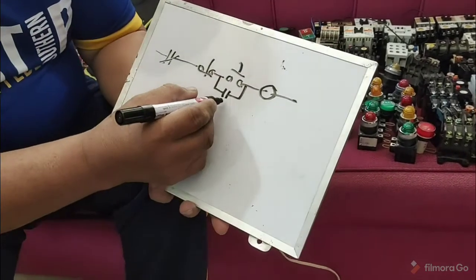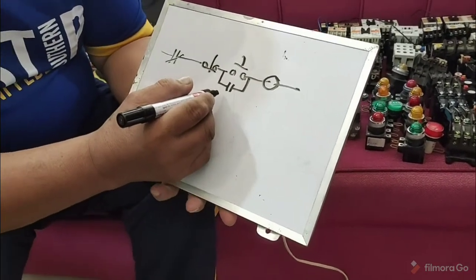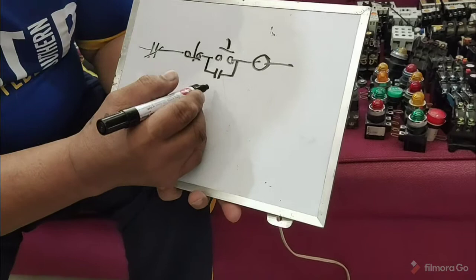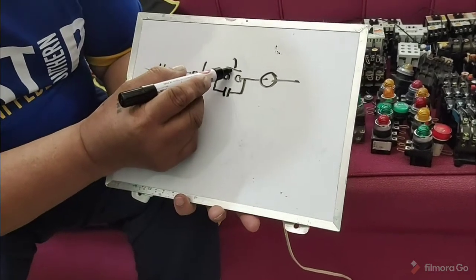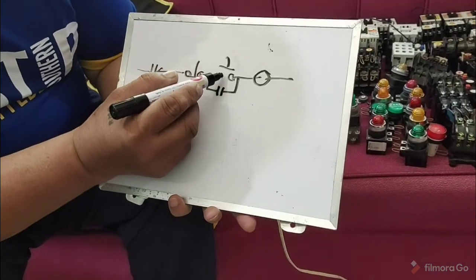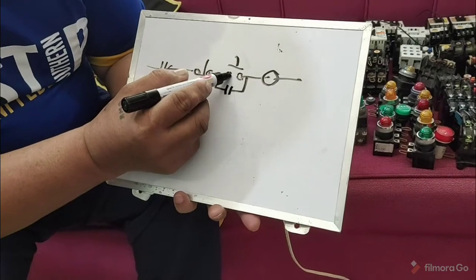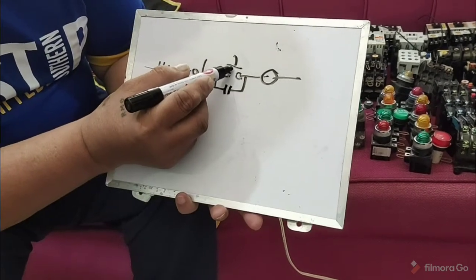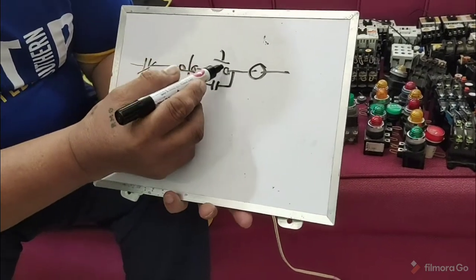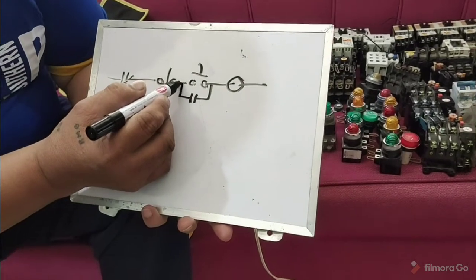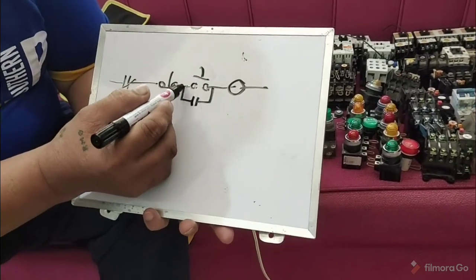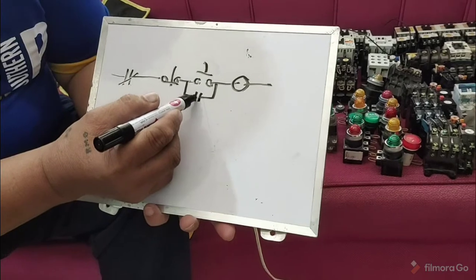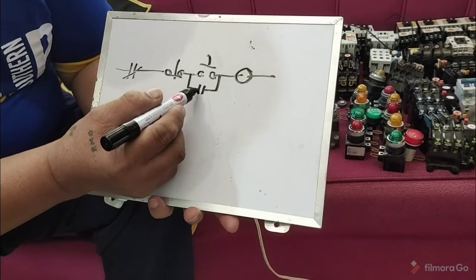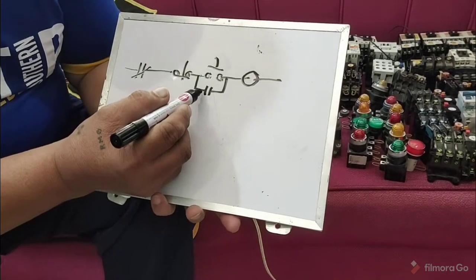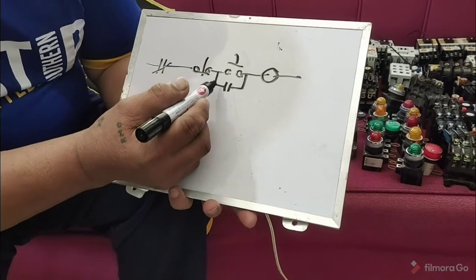Then this is called the holding circuit. Why is it called the holding circuit? Because when you press the start button, this will make contact, but when you release your finger, it will go back to its normal position because of the spring tension. So who will maintain the flow of current? It is now the maintaining contact or the latching contact, an auxiliary normally open contact found in your magnetic contactor.